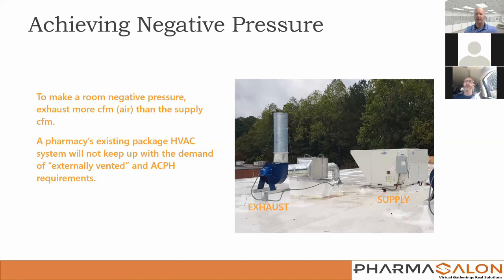All of my slides I think are important, but this one is also very important, because this is the story I got last week. I told them in the very beginning, a friend of mine sent them a price. It was a $28,000 makeup air unit for that piece of equipment, and they cried. And I get it. $28,000 for this clean room air handler. So what they did is they decided to let their HVAC guy talk them into a $6,000 system, 1/4 rather. And now they're calling me again, going, "Bryan, our humidity in the space is going up to 86% consistently," because a standard package air handling system was not meant to do that kind of work.